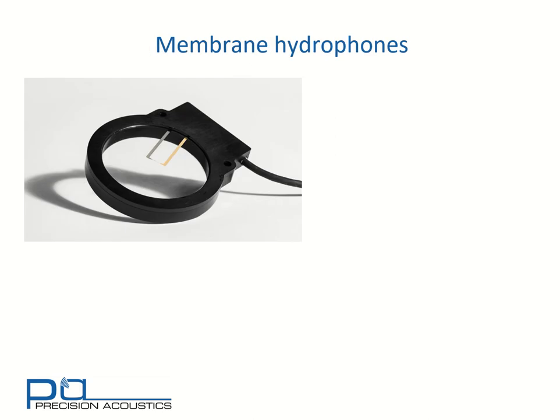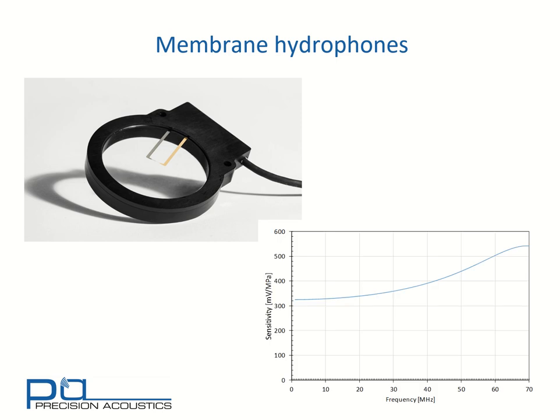Finally, we consider membrane hydrophones. Because these are much larger devices, they don't have the same diffractive resonances that one sees with probe or fibre optic hydrophones. In this case, their only feature in their frequency response is their thickness resonance. For this hydrophone, we see that at about 65 to 70 MHz. Below that, we have a very smoothly varying response, and at very low frequencies — below 30 MHz — there's very little variation as a function of frequency.